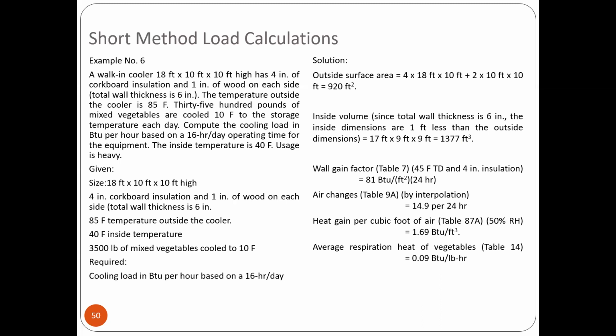Air change, Table 9A by interpolation, is 14.9 per 24 hours. The heat gain per cubic foot of air, Table 87A, at 50% RH is 1.69. The average respiration heat of vegetables is 0.09 BTU per pound per hour.